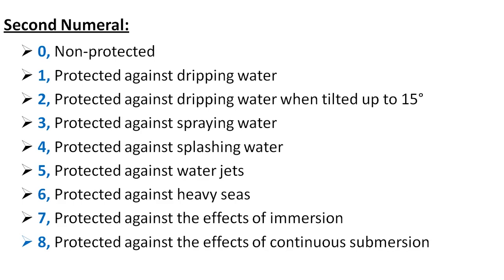Water penetration should not have any effect on the operation of the equipment. When the second numeral is seven, the device is protected against the effects of immersion in water from 15 centimeters to one meter for 30 minutes. When the second numeral is eight, it is protected against continuous immersion in water.